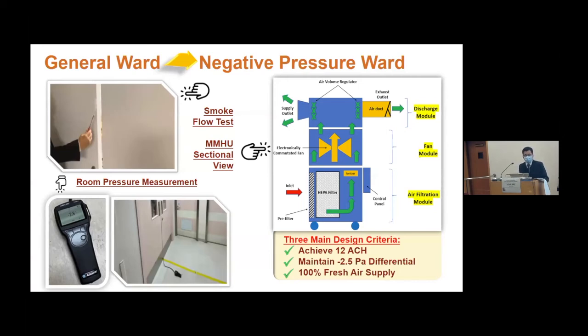On-site testing was carried out at the trial hospitals, and you will see from the pictures that smoke tests were carried out to verify the airflow direction. Measurement of room pressure differential was conducted. Also, the ventilation flow rate was measured to verify that the desired ACH was achieved. Upon verification of the results, the mobile HEPA purification unit went into mass production and had successfully assisted HA to increase the number of isolation facilities and hence the handling capacity for COVID-19 patients. Ever since its first deployment, the second generation of the mobile HEPA purification unit has been integrated with NB-IoT capabilities to receive signals on its operational status, allowing operators to easily monitor its proper operation and carry out any necessary maintenance such as filter replacement.